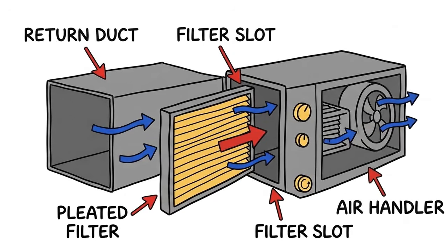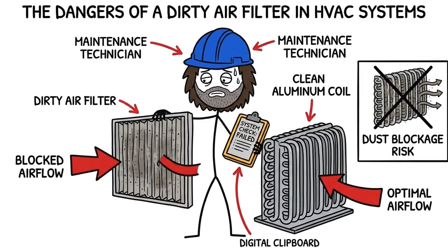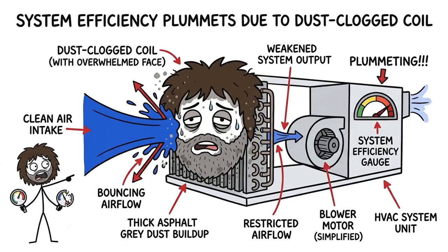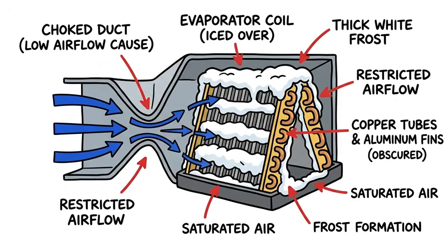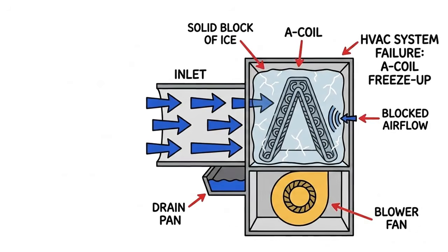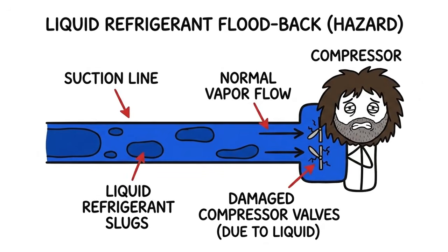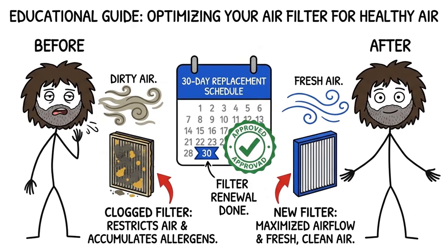into a gas. Because the house air just lost almost all of its thermal energy to the refrigerant, its temperature drops by 15 to 20 degrees. This temperature drop between return air and supply air is called the temperature split, or delta T. If your system has a healthy 18 to 20 degree temperature split, your refrigeration cycle is functioning efficiently. This chilled, refreshed air is then pushed out through your home's insulated supply ducts and back into your living spaces.